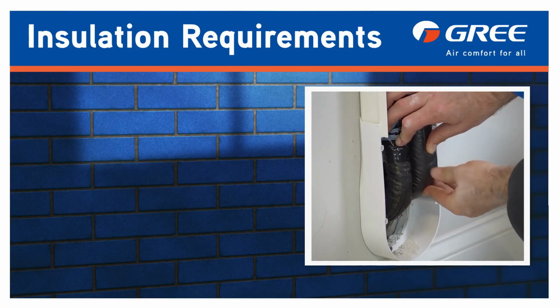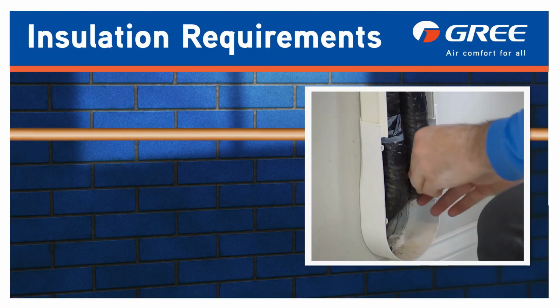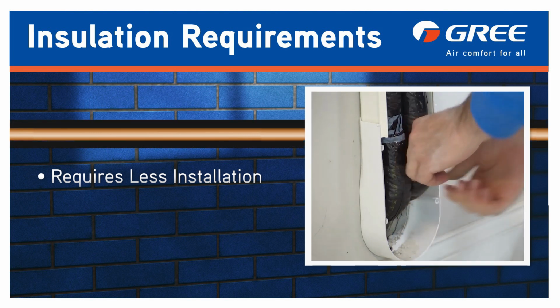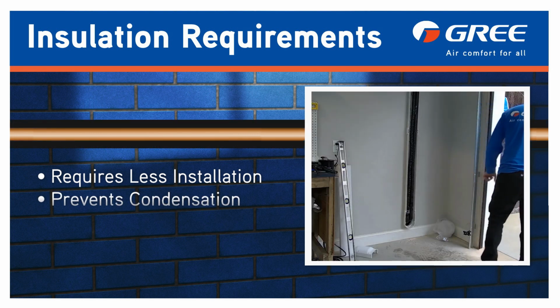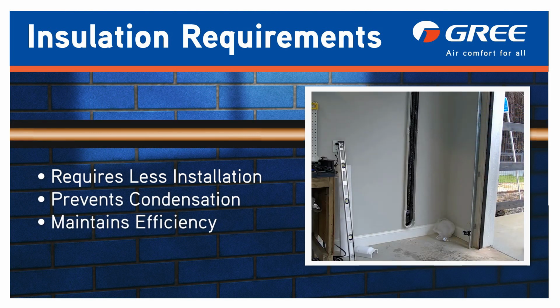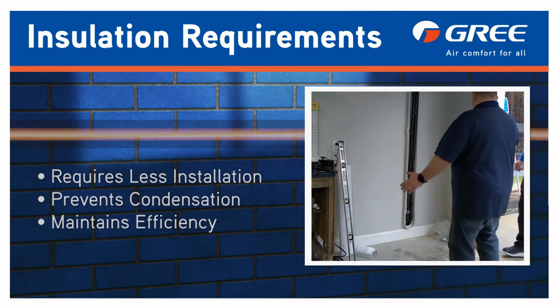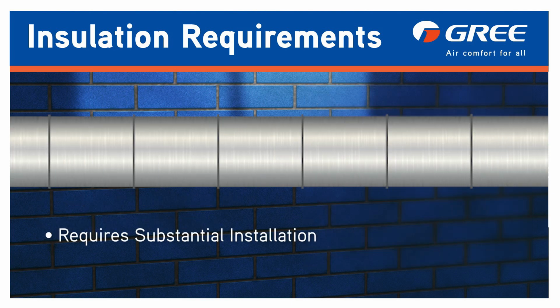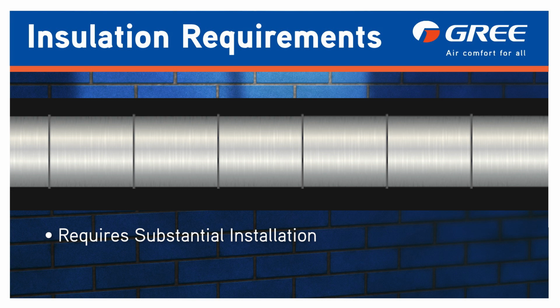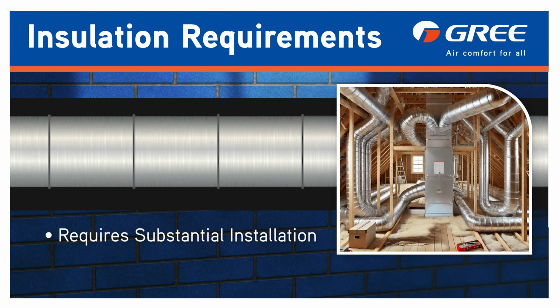Now, something not often considered: insulation. Refrigerant lines typically require less insulation. Some is needed to prevent condensation and maintain efficiency, but it's generally easier to insulate small diameter lines. Ductwork, on the other hand, requires substantial insulation, especially in unconditioned spaces like attics and crawl spaces.